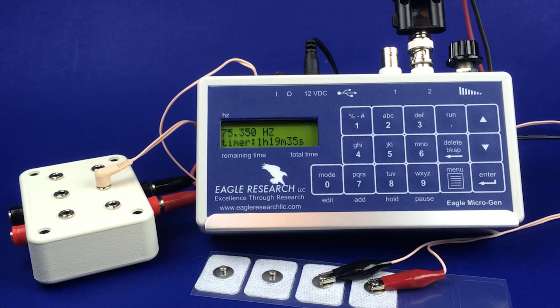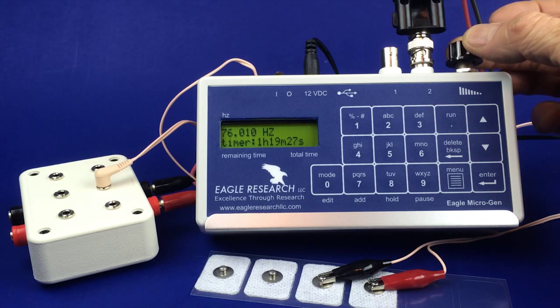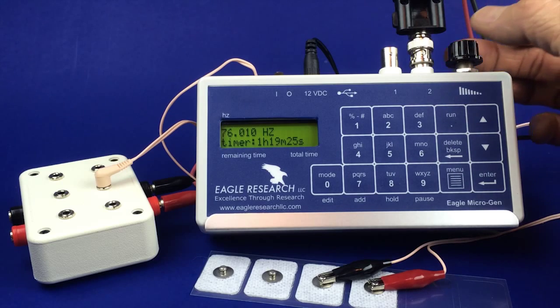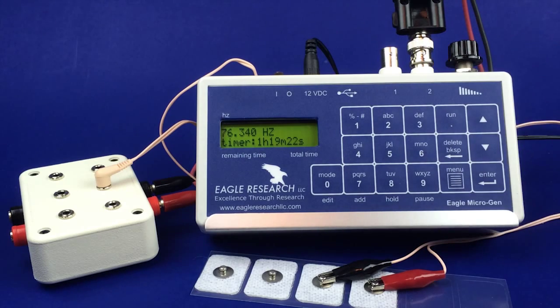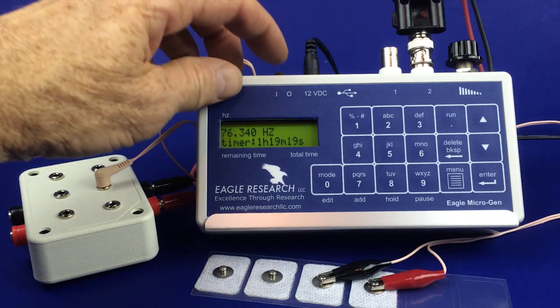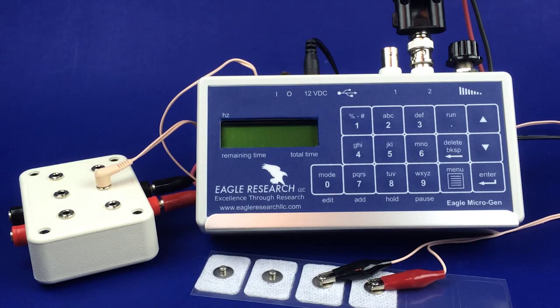Once the current has stopped coming to the electrode patches, that you're at the end of your program, then it's always a good practice to simply reach up and turn the intensity all the way down so the next person has it set in the right position. And then simply push the button to the right, and that shuts the power off to the unit. Might also point out that if you do use that pause button, always remember to disconnect yourself from the unit, undo the electrode patches so you don't end up walking away and dragging the whole unit off the table.